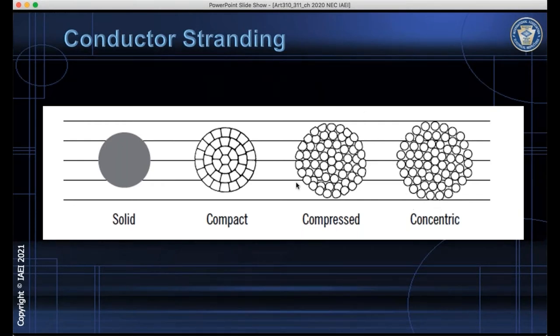If you look at, for example, 600 volt copper building wire, most of that is compressed. And so what happens is the manufacturer takes all of those strands, they twist them together, and then they apply some compression using a die during the process to reduce the outer diameter by a small amount. It's usually about 3% smaller than a concentric conductor.